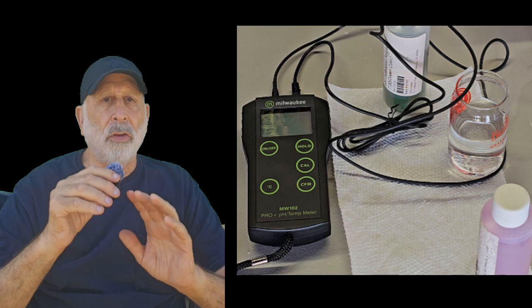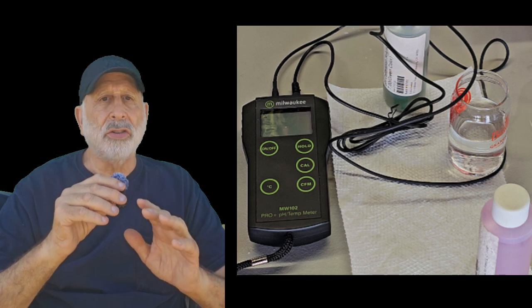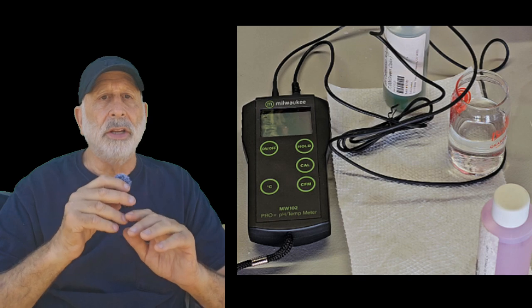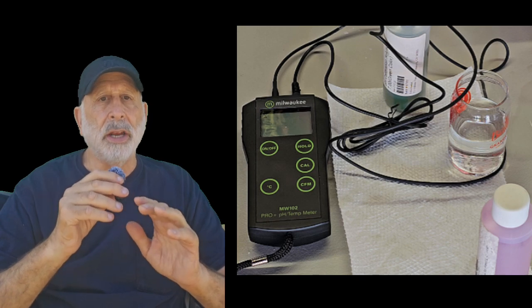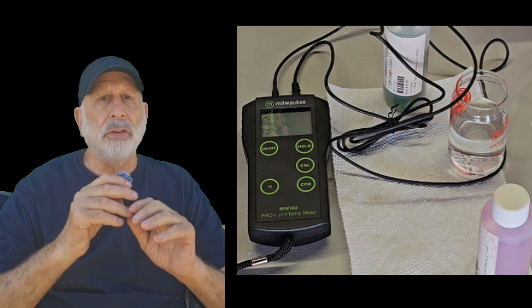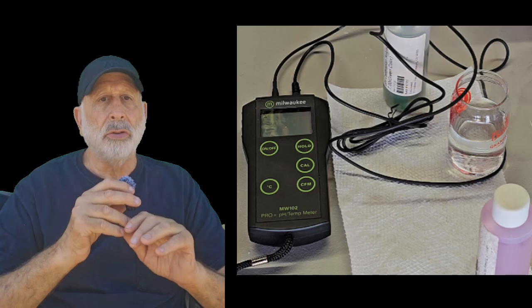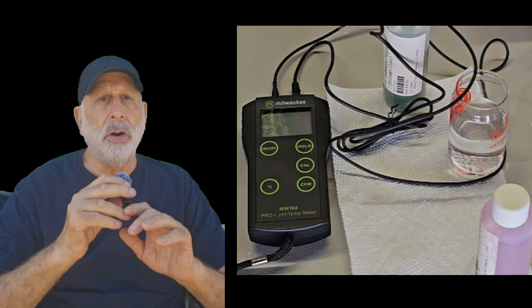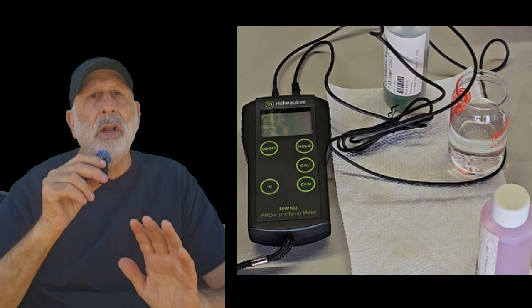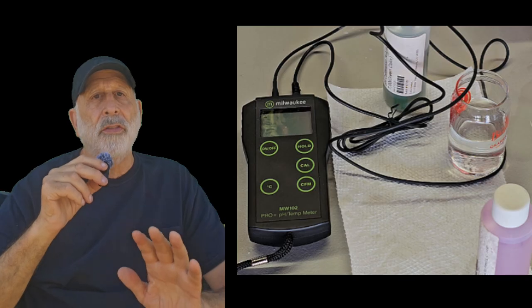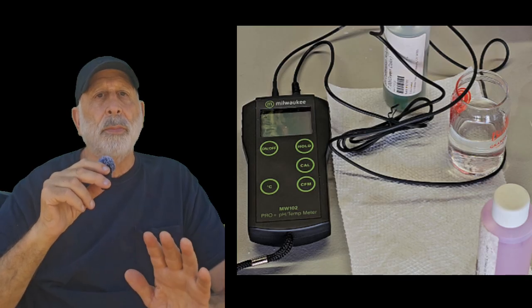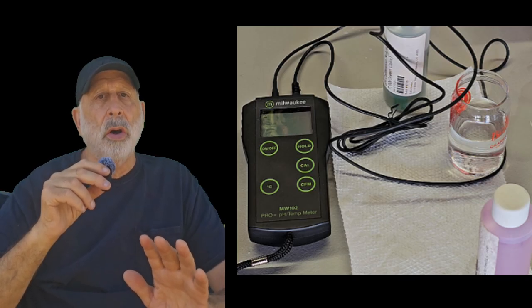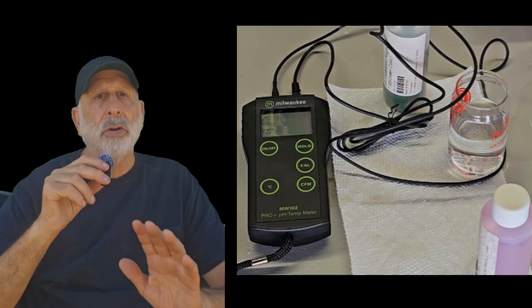Let's just talk about the water for a second. RO water is reverse osmosis water, and DI water just means deionized water. DI water is very pure with almost no minerals, which is why pH readings can be harder to stabilize. They're both very clean, purified waters with very few minerals in them. That's why the pH readings in DI and RO water could drift around or take longer to settle.